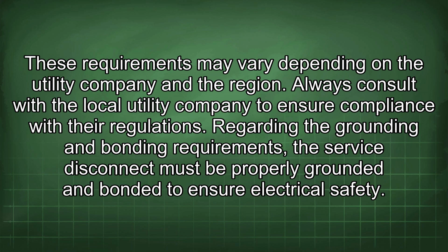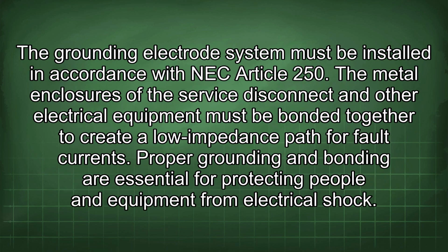Regarding the grounding and bonding requirements, the service disconnect must be properly grounded and bonded to ensure electrical safety. The grounding electrode system must be installed in accordance with NEC Article 250. The metal enclosures of the service disconnect and other electrical equipment must be bonded together to create a low impedance path for fault currents. Proper grounding and bonding are essential for protecting people and equipment from electrical shock.